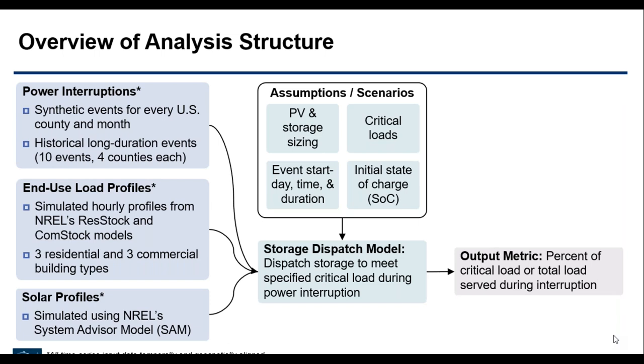In addition, we do a bit of empirical analysis using historical long duration events, selecting 10 of them encompassing four specific counties for each event. In those, we reflect the empirical start time and duration of the particular events, and we also align with the weather patterns that existed at that time. The idea is that since these historical events are largely weather driven or extreme weather events, the performance of PV is largely impacted by the particular weather conditions. This differs from the synthetic events, where we don't make particular assumptions about the status of PV performance.